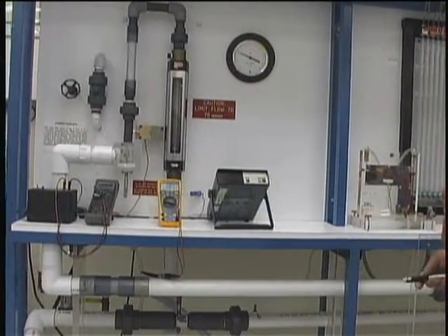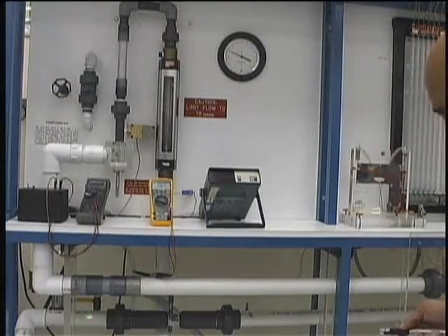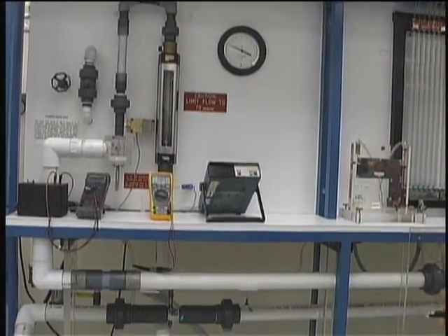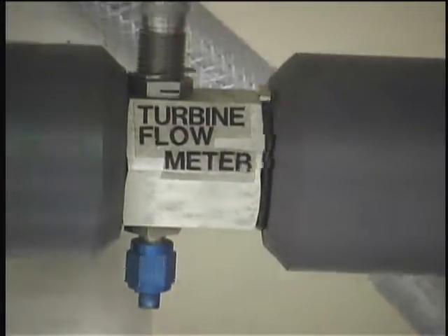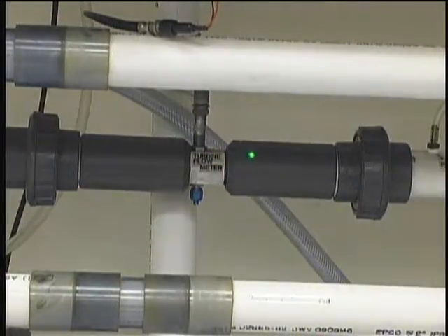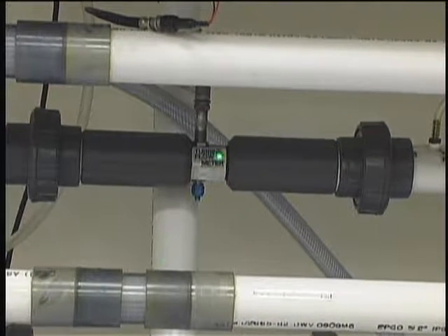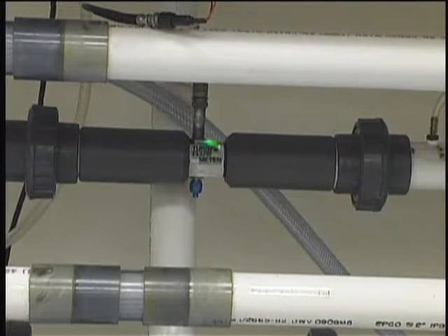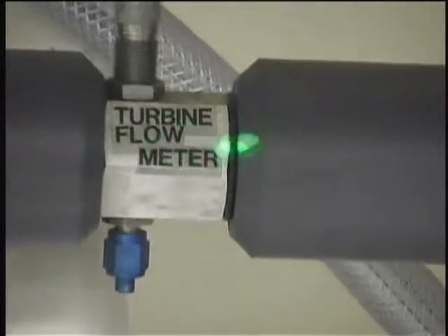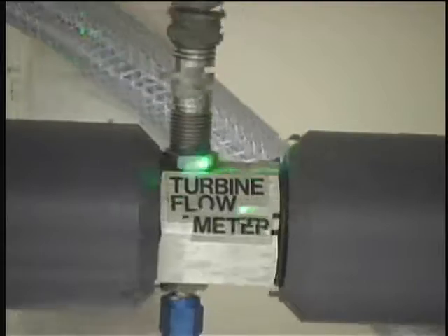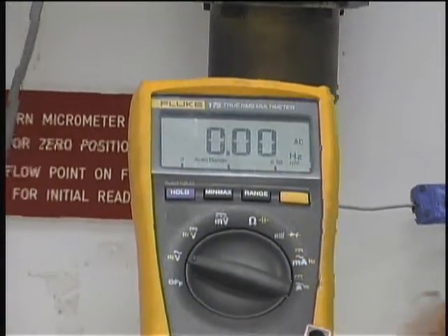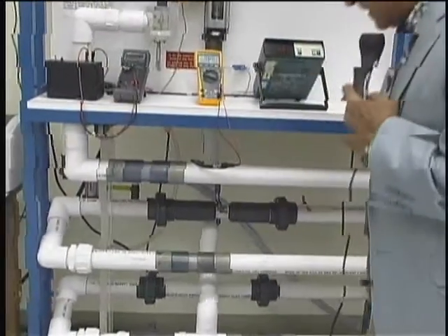As the air goes through, it will continue down here where it will go through a turbine flow meter. If we zoom in here, the PVC pipe is sectioned, and the flow meter is connected to the sections where the turbine is inside. As it rotates, it will induce an electromagnetic pulse at every rotation that can be measured. So this measures the frequency of each pulse, and the frequency you can read off here. It gives you how many rotations per second of that wheel that is moving.